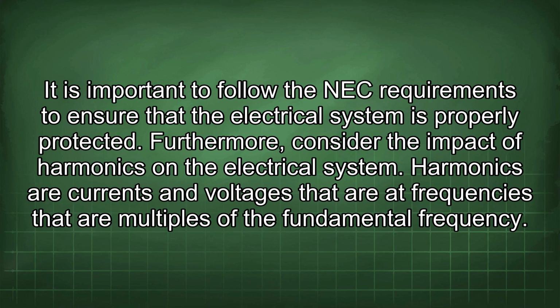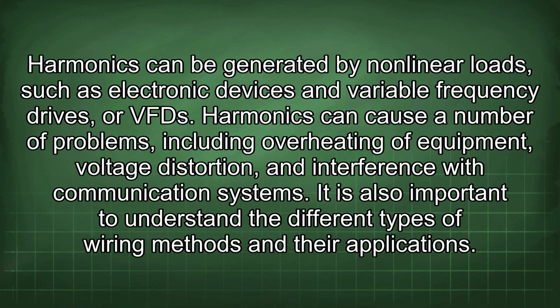Furthermore, consider the impact of harmonics on the electrical system. Harmonics are currents and voltages that are at frequencies that are multiples of the fundamental frequency. Harmonics can be generated by nonlinear loads such as electronic devices and variable frequency drives, or VFDs. Harmonics can cause a number of problems, including overheating of equipment, voltage distortion, and interference with communication systems.